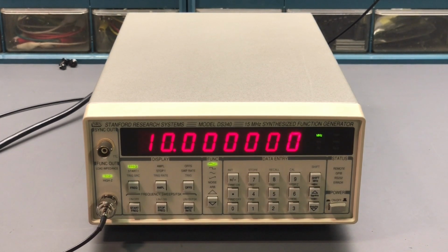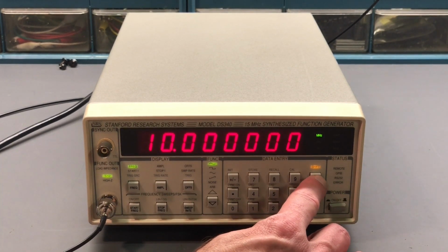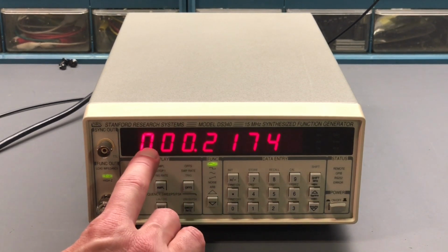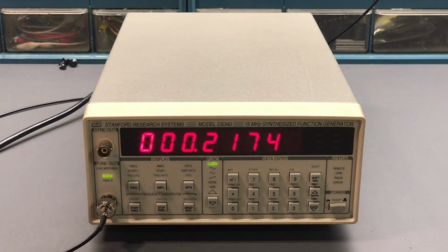And it is really quite simple. First of all, you need to have the jumper on the main circuit board set to the position I previously talked about, which gives access to the cal bytes. And then you just press Shift and the number 9 key, and that brings you into the cal byte settings. So on the left-hand side of the decimal point, this is the cal byte, and cal byte 0 is actually the one that we'll be making the adjustment to. That's for the main oscillator frequency. And on the right-hand side, that's the cal byte value. 2174 is the factory preset, basically. It's the value that the instrument left the factory with.